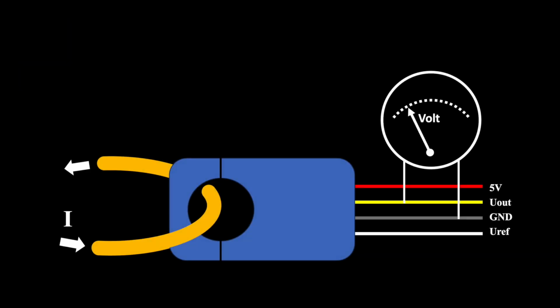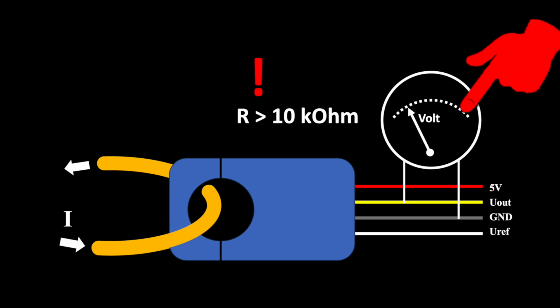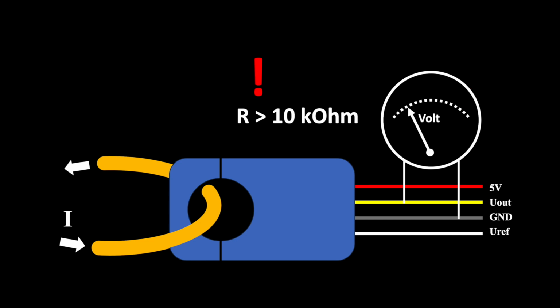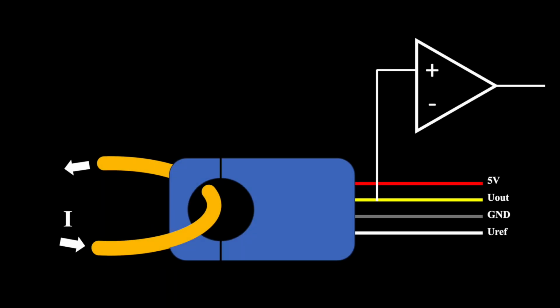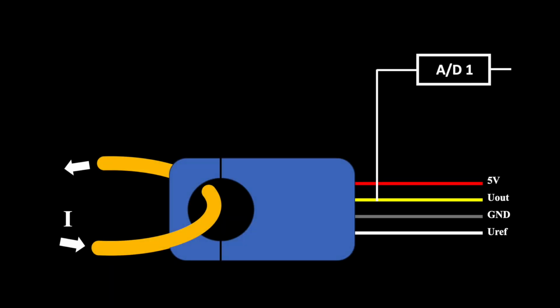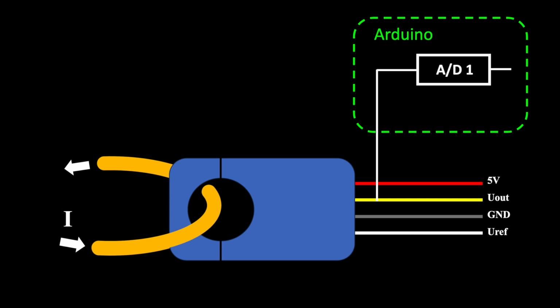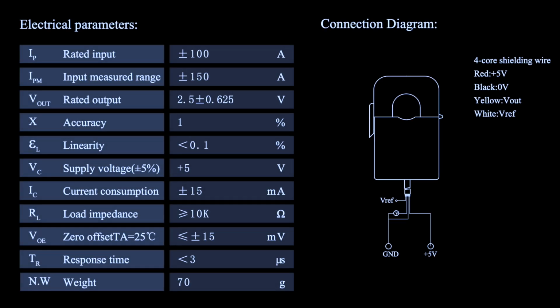This value is telling us that the sensor output load needs to be minimum 10 kilo-ohm. According to Ohm's law, that's only 250 microamperes at 2.5 volts output. Not enough to drive a typical display instrument drawing 1 milliampere at full scale. High impedance inputs of operational amplifiers or AD converters are ideal for this purpose. The maximum zero offset of 15 millivolts is corresponding to approximately 2% deviation. You can also compensate it by calibration.